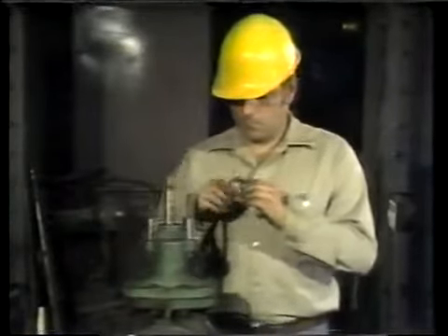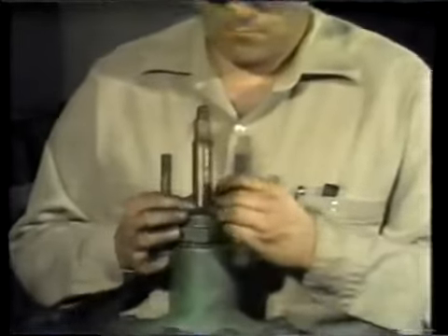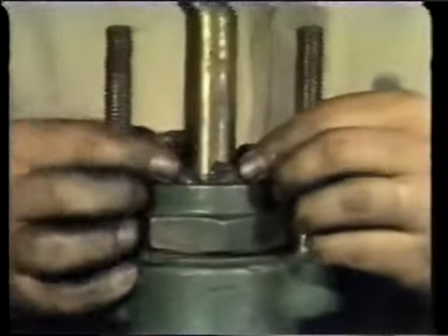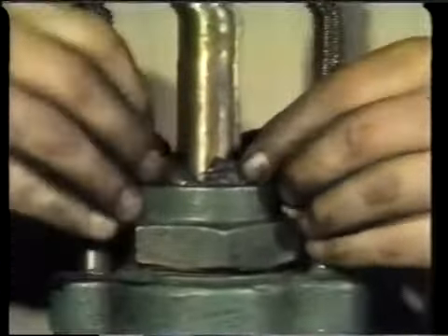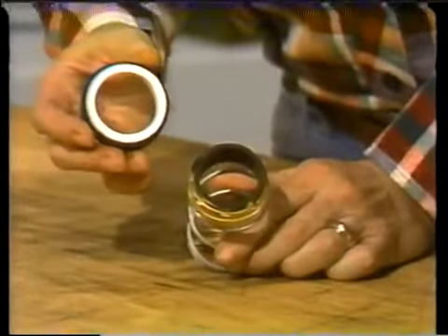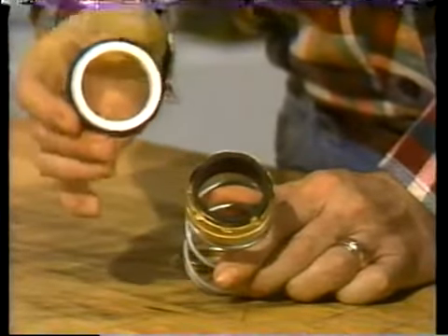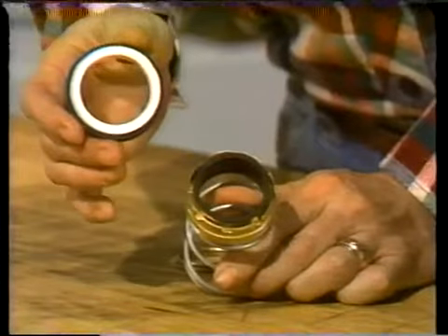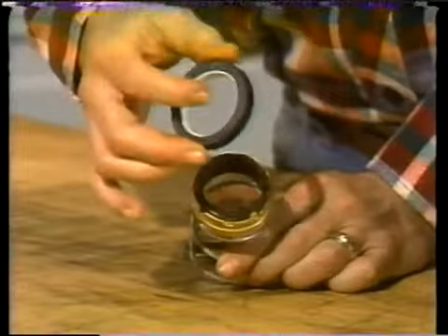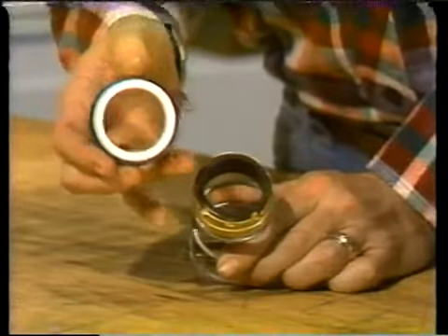If you have to remove some packing, it's almost as easy to replace it with new packing as it is to reuse the old packing. This will depend on the availability and cost of the packing. Now, mechanical seals are one area where you can't compromise. If one of the faces on a mechanical seal needs replacing, both faces must be replaced. The two faces wear together during operation, and a new face is not going to seat properly against the old one.